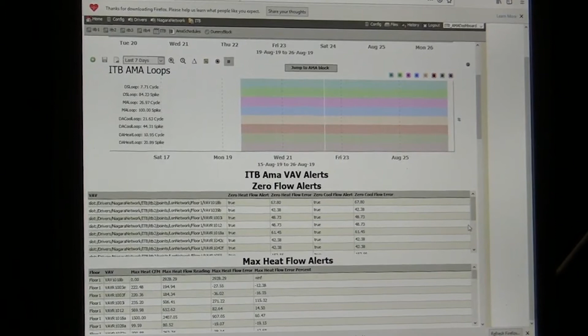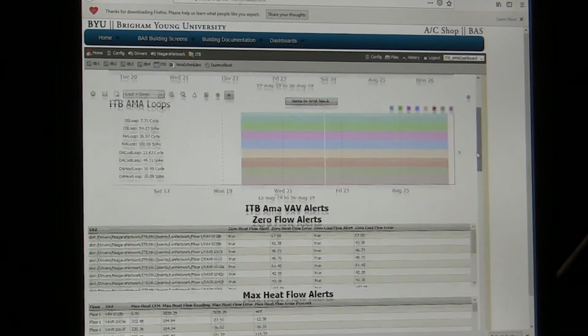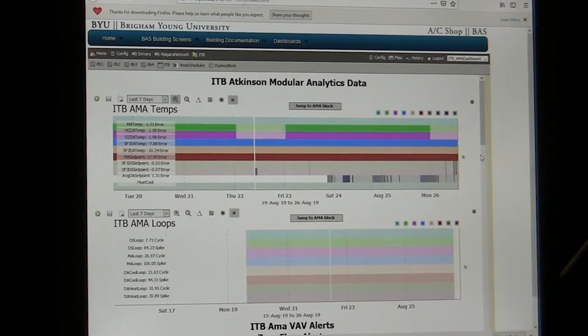We have found places where we get areas that are overcooling because the damper doesn't shut. But maybe it's an IT closet that no one's in. But we're at 55, 58, 60 degrees all the time when it doesn't need to be that cold. So we could be saving fan horsepower and cooling by fixing those problems. So it's one of the things that analytics helps us to find, some of those errors. So that's part of the reason we picked this building to look at, because some of those things came out as we looked at this and we did a review a week ago. And so, any other questions about that? So thanks.